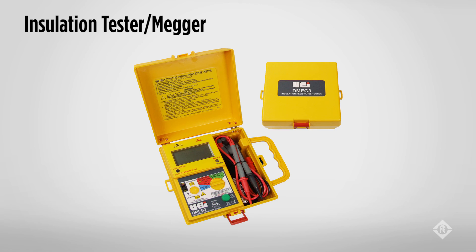When testing for a ground fault or failure of insulation, a megger is a must. To test insulation on wire or motor, voltage higher than the VOM, volt ohmmeter, can provide is needed. Franklin motors are rated for a thousand volts. To test them and the wiring, we recommend the test be run at a thousand volts. To run the test, hook your test leads between the power leads you want to check and the green ground wire. The reading may be in millions of ohms. Since the test voltage is a thousand volts, use the alligator clips to hold the test leads to the wires. A ground fault is more than a problem with the system. It is a danger to the user. The longer the wire, the greater the resistance and therefore the greater need for larger wire.